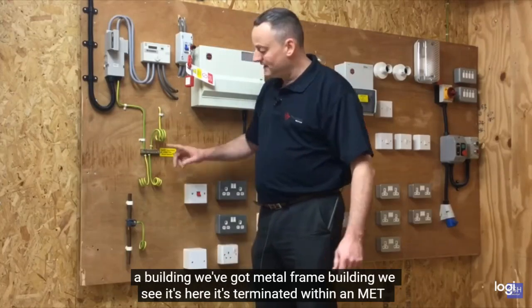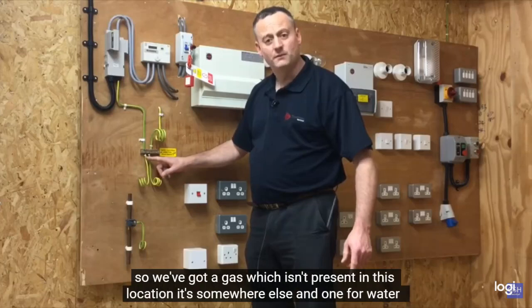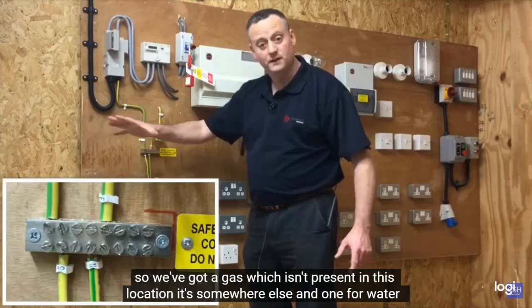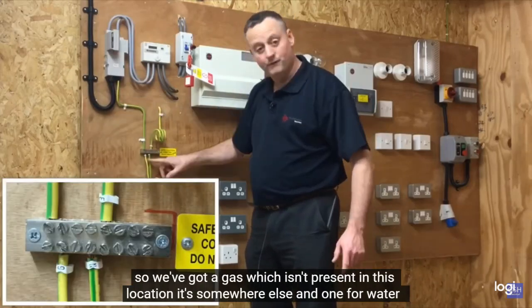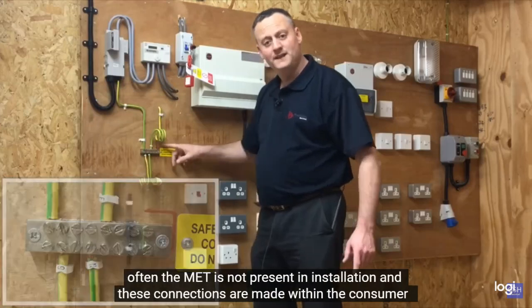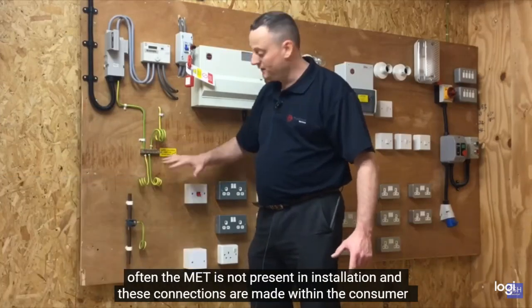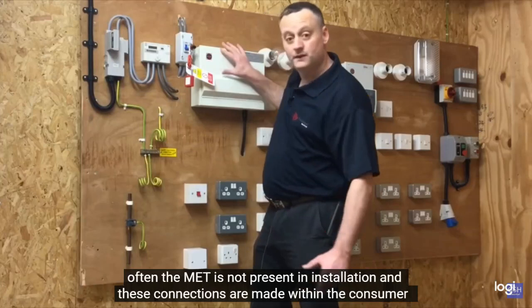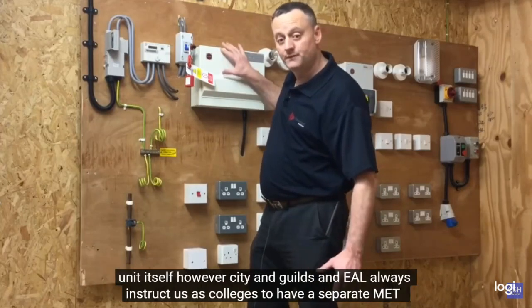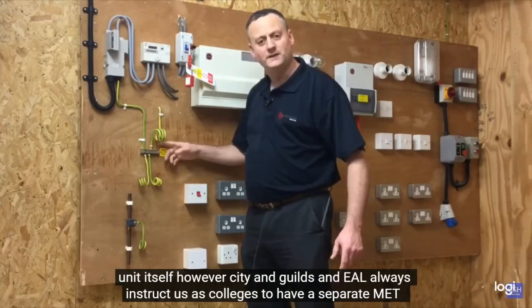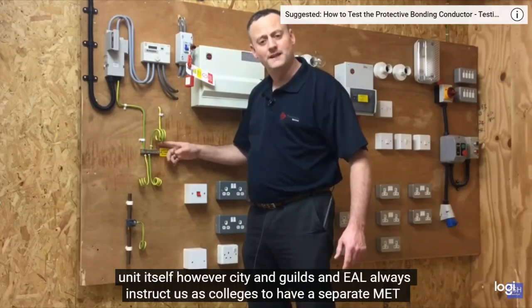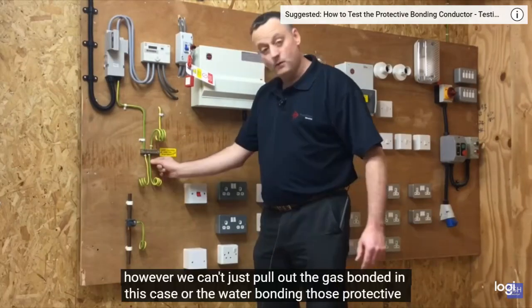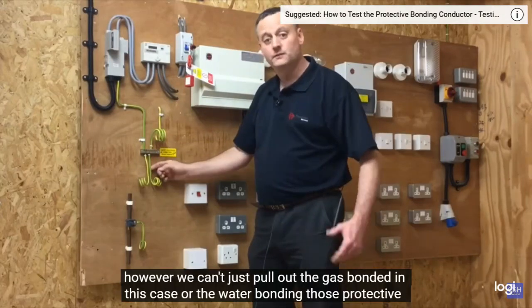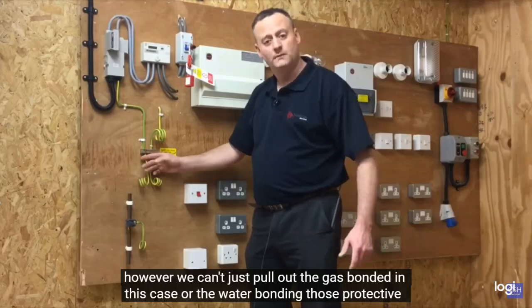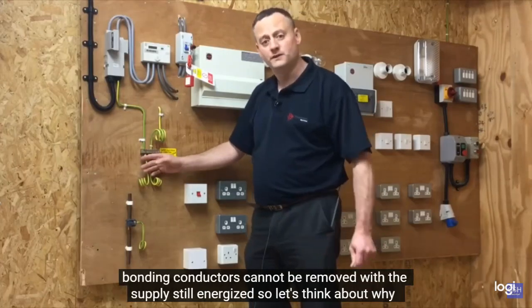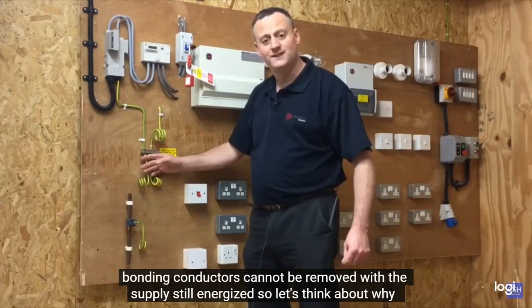We see it here, it's terminated within an MET, so we've got a gas connection, which isn't present in this location, it's somewhere else, and one for water. Often the MET is not present in the installation, and these connections are made within the consumer's unit itself. However, City and Guilds and EAL always instruct us as colleges to have a separate MET. However, we can't just pull out the gas bonding in this case, or the water bonding. Those protective bonding conductors cannot be removed with the supply still energised.